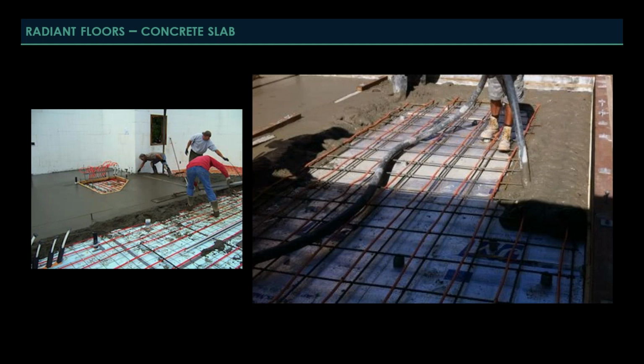So here's a couple examples of radiant floor slabs actually being poured, and to be quite honest, it's not that dissimilar from simply pouring a normal concrete slab. Care must be taken that the tubing is appropriately protected and secured into place, and then the concrete is poured on top. And in both images, you can see the layer of insulation below the radiant tubing.